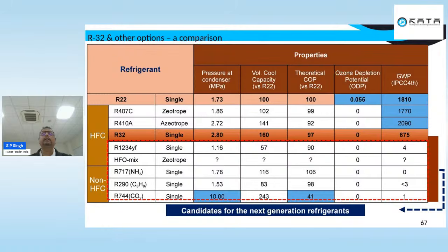Suppose 1 kg of refrigerant amount is in the system. Somehow we have to make our heat exchanger and compressor so that minimum refrigerant is used. At present, Daikin uses 600 grams of refrigerant for a 1 TR product. To reduce this GWP, we have to reduce the amount of refrigerant—we can come down to 50 or 100 grams. The moment we reduce that amount while keeping the refrigerant effect intact, without affecting that effect, if we can reduce the GWP by reducing the amount of refrigerant, then we can say we have modified it.